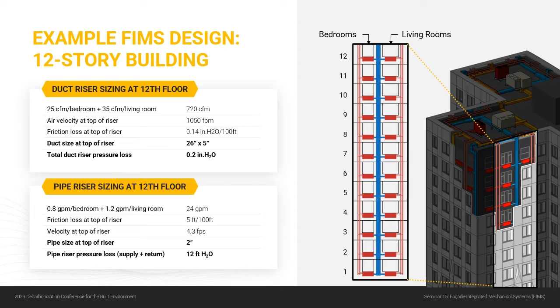We're assuming that that duct is supplying 60 CFM of outside air at each floor, which is high, but we're just being conservative. And if we use standard low-pressure ductwork sizing, we end up with a 26 by 5-inch duct and a very low pressure drop on that duct. And then also looking at the pipe, again being pretty conservative about the amount of GPM that it actually has to supply, and using standard sizing criteria for low pressure pipe, you end up with a 2-inch pipe.